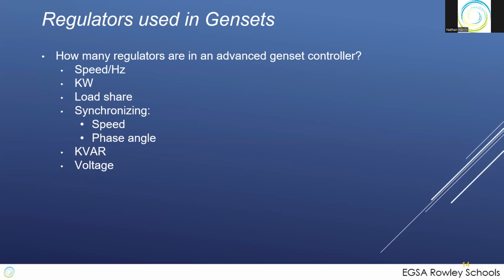So several of them could be in today's genset controllers, and they all have PID values that have to be tuned. So don't underestimate the value to your system of a good tune-up, and don't overlook any of these regulators when you're doing your tune-up, because maybe you're only running a gen and load combination today, but tomorrow you may run multiple gens in parallel with each other and may have to come back and retune them, because if you have two or three generators feeding the same load, their response times need to be very close.